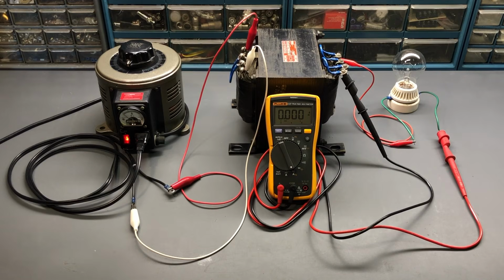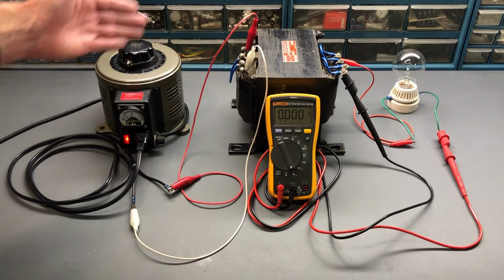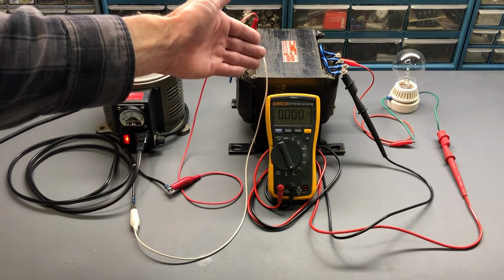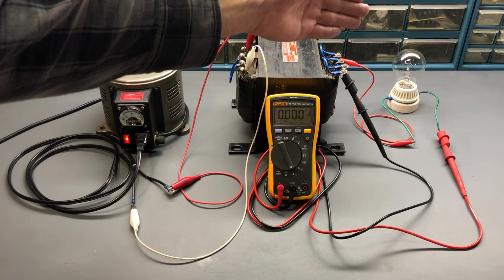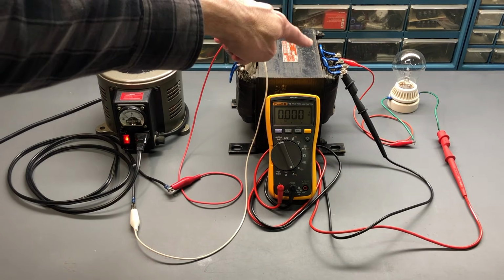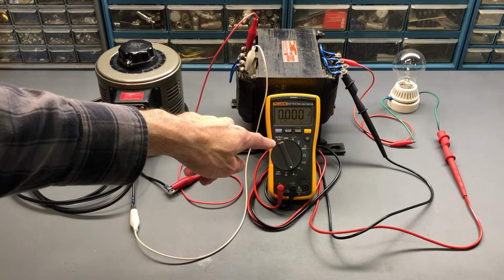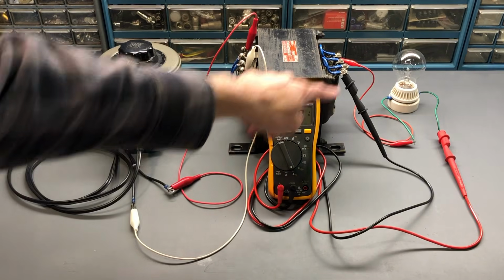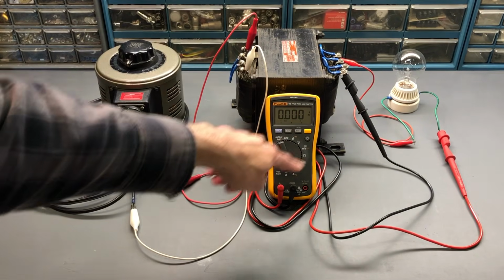Here we are looking at the third configuration for the isolated dim bulb tester. In this configuration, we have the Variac first, the isolation transformer second, and then the incandescent bulb connected on the secondary of the isolation transformer. The device under test, in this case our amp meter, is connected from the other side of the incandescent bulb, and it comes through the amp meter and then back to the secondary winding.